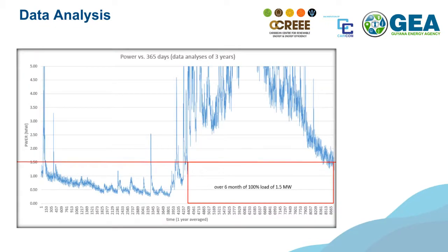Maybe this is a real leveling logger - you see here the hours. This is 1 year, 8,000 hours, but we measure every 10 or 20 minutes, so we have much more data. This is the average of 3 years leveling, and I translated it directly to power in this example.